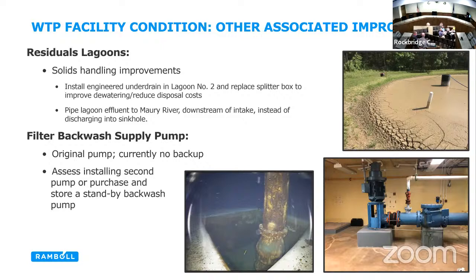Filter backwash supply pump is a critical asset. It's currently the only pump available to backwash the filters, and it's an original pump. So the recommendation is to either make improvements to the clear well in order to install a second pump, or have a second pump on close standby to replace this one when it fails.